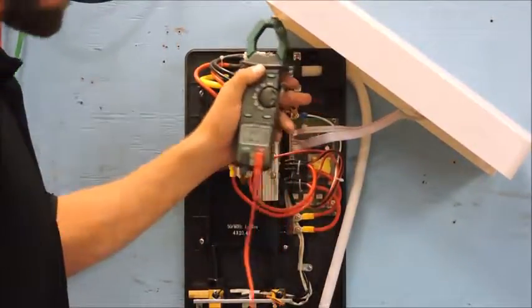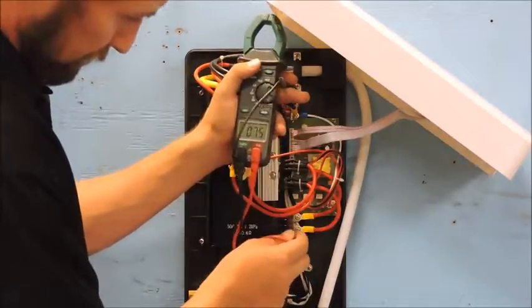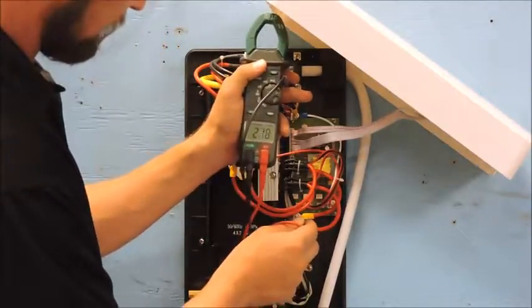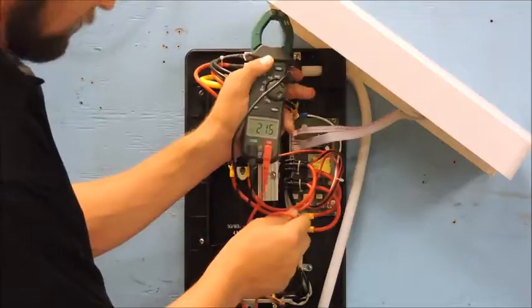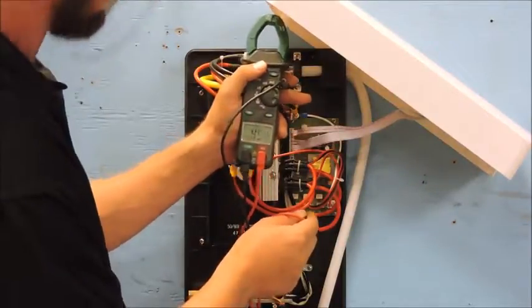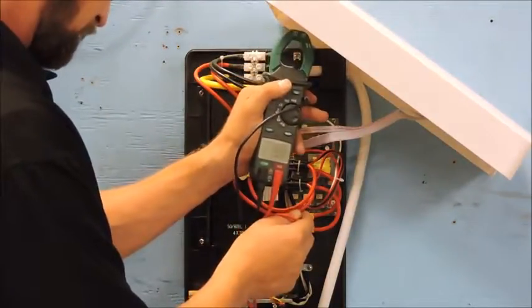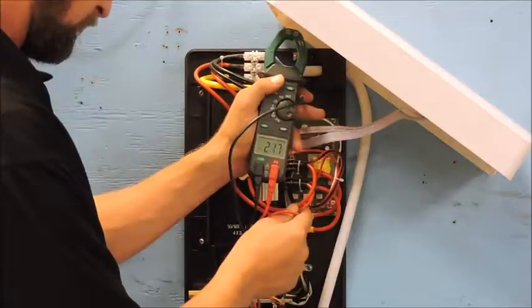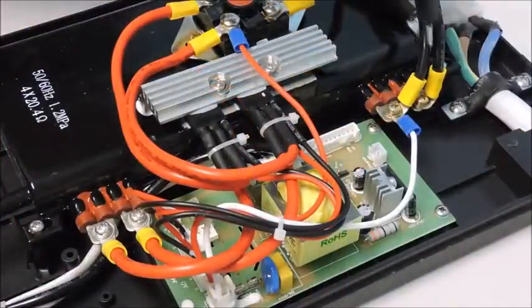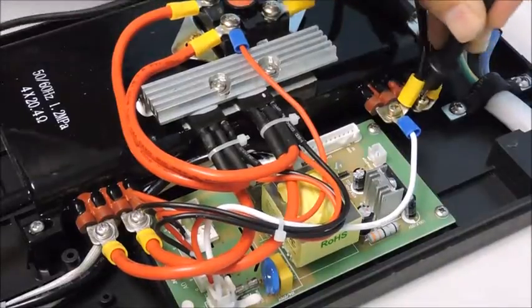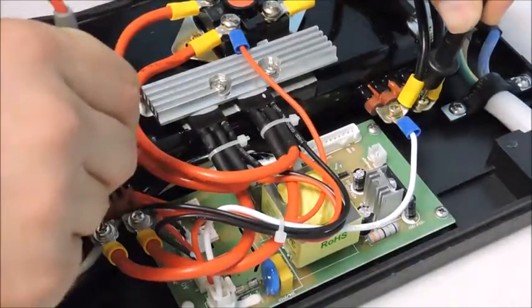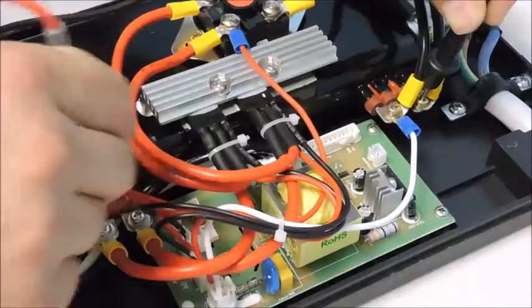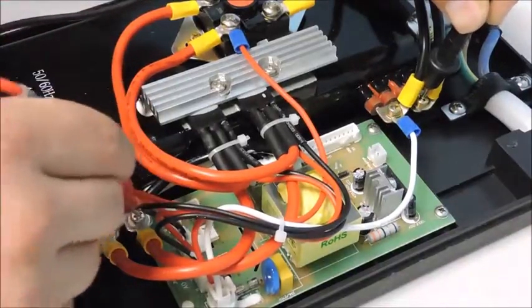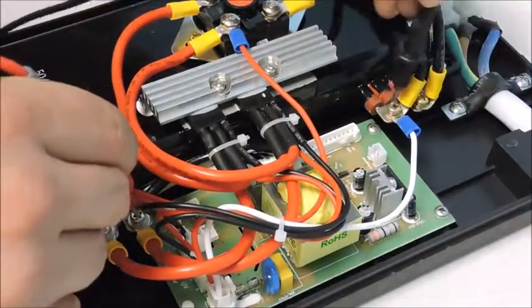Next, we will confirm power running through the unit. Place the black probe on the ground at the terminal block, then the red probe on each electrical connection on the side of the heat exchange. There are 4 in total. Each location should read roughly 110 volts. If there's a failure on one of these points, then replace the corresponding triac. Confirm 220 power by putting the probes on both outer electrical connections on the side of the heat exchange, followed by the 2 inner connections.